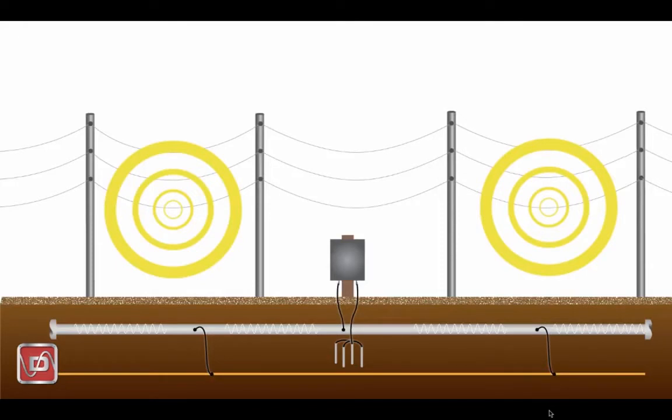You'll remember that a decoupler both isolates and grounds simultaneously. We can both isolate the CP current while simultaneously bonding the pipeline to ground for safety. As you can see, with the decouplers installed, our cathodically protected pipe is safely isolated from the grounding system for direct current, while still safely bonding for alternating current. Our pipeline and workers are protected from AC induction, and if an AC fault and lightning event occurred, the device would temporarily switch to a completely shorted mode to provide worker protection. Yet, our cathodic protection system will continue to operate as if there is no safety bonding to ground.